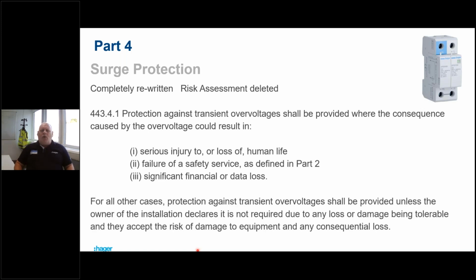So for all other cases, protection against transient overvoltage shall be provided unless the owner of the installation declares it is not required due to any loss or damage being tolerable, and they accept the risk of damage to equipment and any consequential loss. Okay, so that's a bit of a get-out clause for us. We can only use that if we don't fall into one of the 3 categories above.